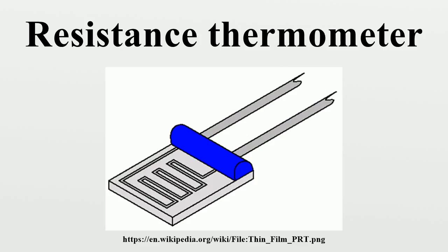This temperature coefficient of resistance is called alpha. The equation below defines alpha. Its units are ohm per ohm per degree C. The resistance of the sensor at 0 degrees Celsius. The resistance of the sensor at 100 degrees Celsius.